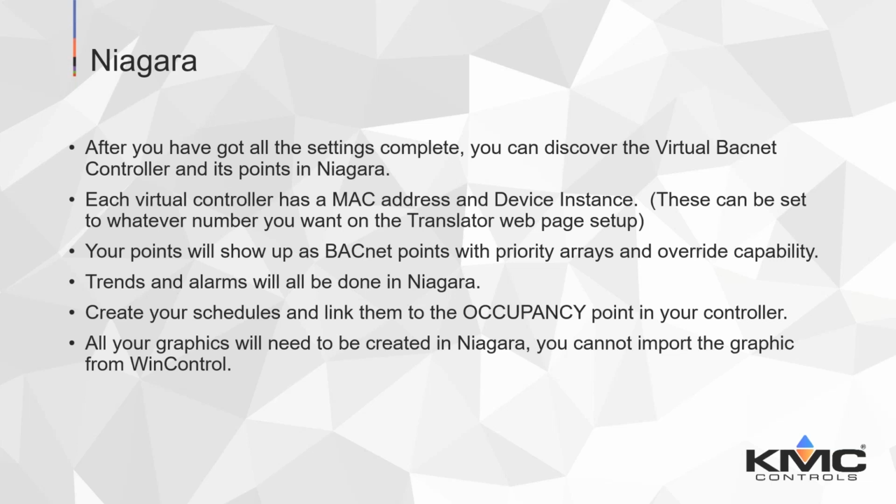Yeah. The other option I would say, and again, this is where it's really helpful to review these installations with a sales engineer. If this question came to me, I would ask, do I have Niagara at each one of these sites? It would be easy if I already have Niagara at each site. I want the translator locally, and then I only have BACnet between the translator and Niagara locally, and Niagara would then be communicating across those states to the different jobs.